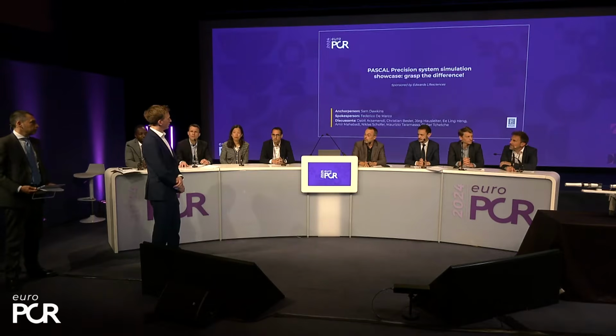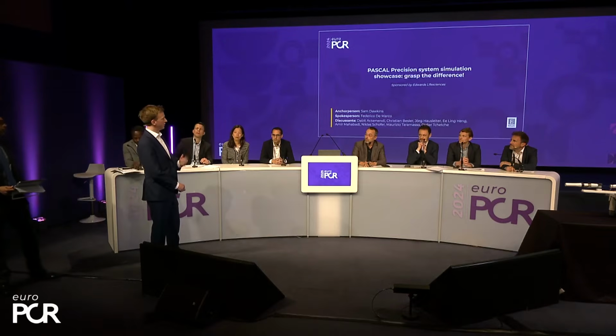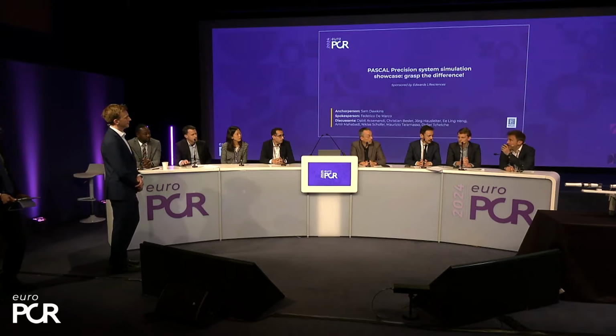I think that's a really important point, isn't it? Because the independent grasping aspect is good, firstly, for capturing the leaflet, but also if you do it one at a time, you can then focus on the imaging. The imaging can be difficult, and focusing on one paddle at a time actually makes a really big difference to your confidence that you've got a decent grasp. And there's one additional aspect: because of this maneuvering, swinging from one leaflet to the other, you might get even more leaflet into the device, and your analog plus TEER effect might be significantly higher. And the positive thing is that you don't miss the leaflet. Yeah, you focus.